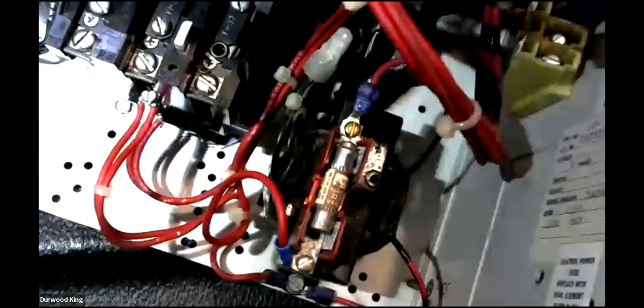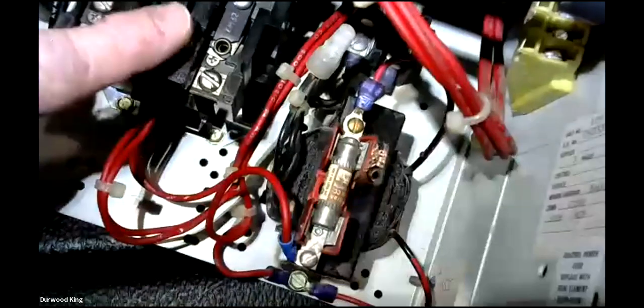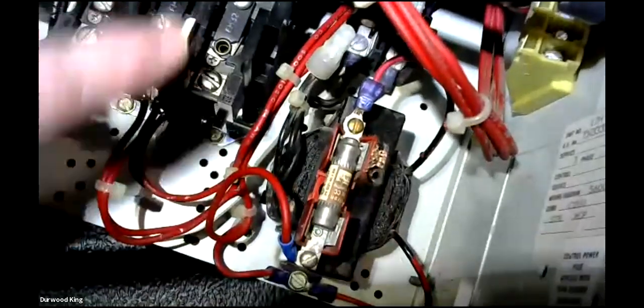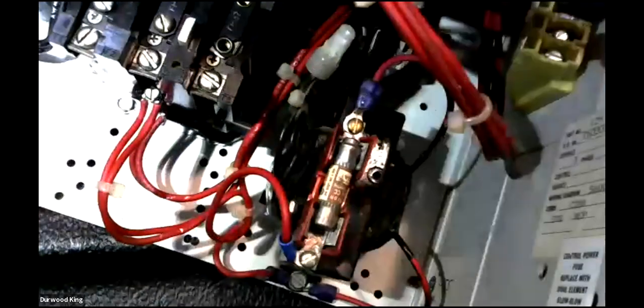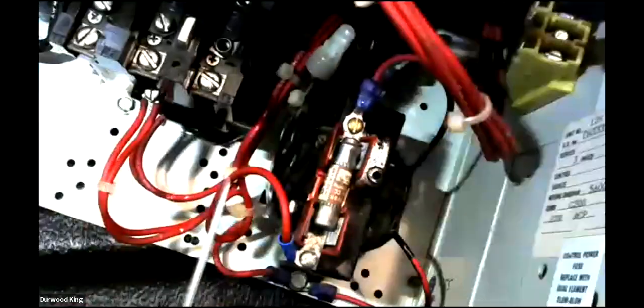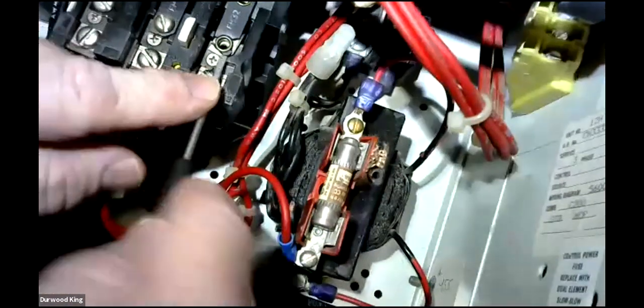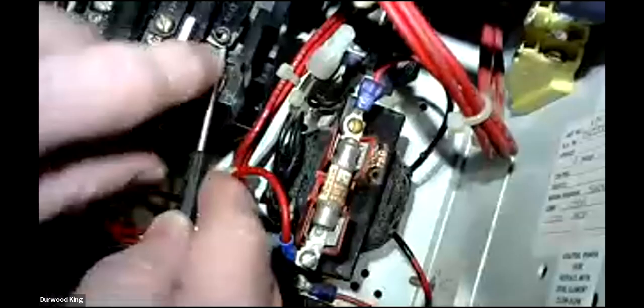Now, let's pull one of these out and let you see what it looks like. So what can happen is somebody can reset it so many times that it actually burns one of these heaters open, and it will never reset. So we're talking an operator, Jamie, that kept resetting it. He snuck in the panel and he didn't tell you, but he's already reset it 10 times, and you've actually got bad bearings in the motor. He keeps resetting it. And then after it won't reset, then he finally calls you. So if you look now, can you see what I'm doing here? Yeah. So look, you got to gouge it out with a screwdriver.